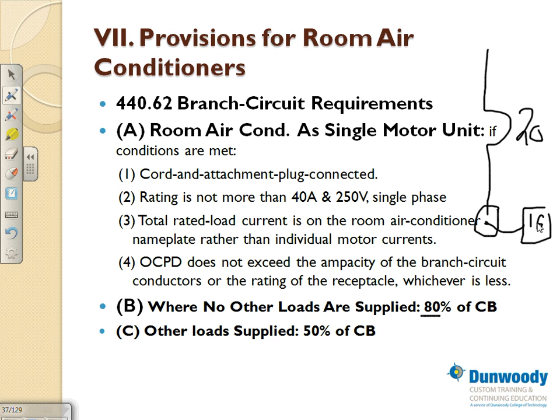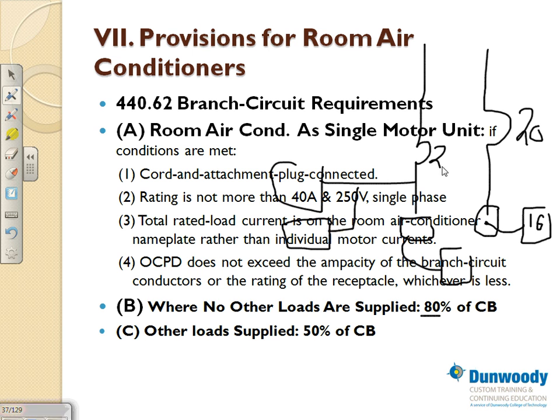This is for a poor man's job, if you have a circuit that's feeding other loads. So suppose I have a circuit coming over here and feeding the air conditioner plug. I'm plugging my air conditioner here, and also somewhere here going to a light, feeding multiple lights, coming here and feeding a receptacle, right? It's shared by multiple things. Then you are limited to 50% of the circuit breaker. If this circuit breaker was 20 amp, then your air conditioner cannot be more than 10 amps. The problem is how are you going to enforce this? It's portable equipment. People can plug it in.